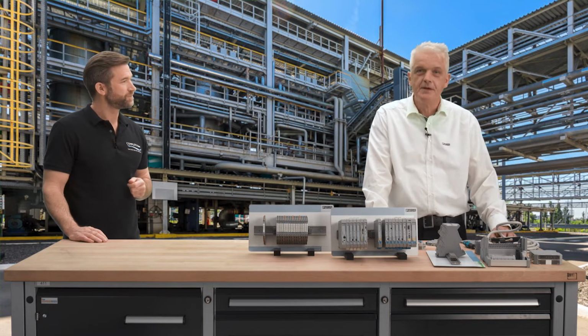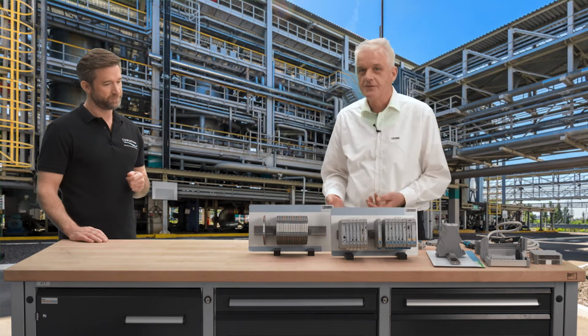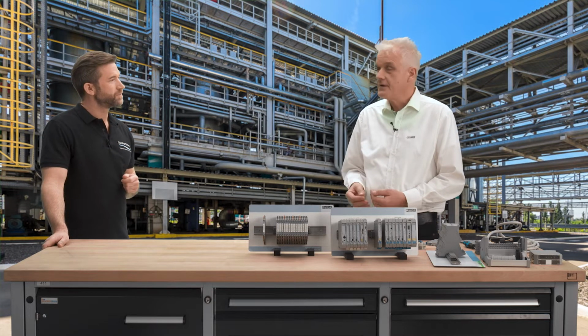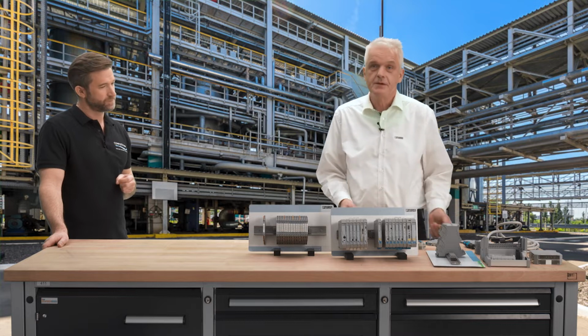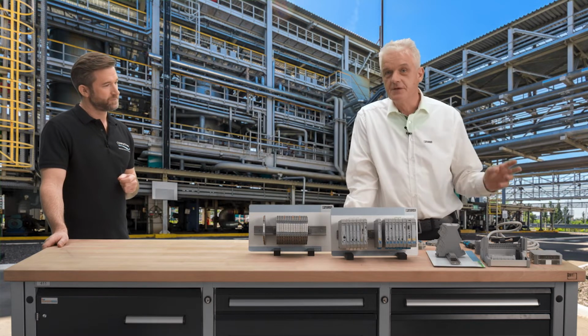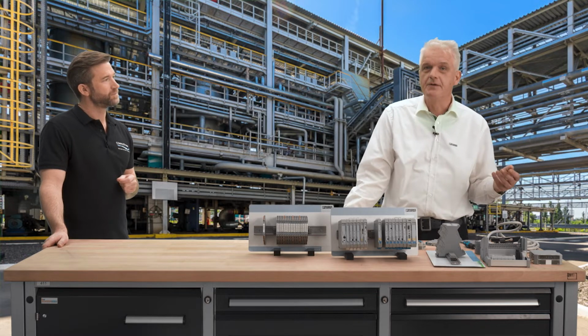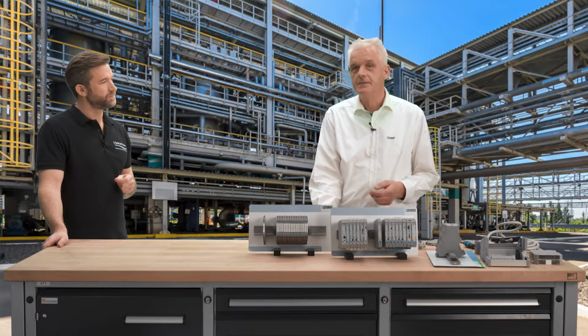Yes, of course. Signal conditioners fulfill, depending on the specific application, a variety of tasks. Signal conversion is the first one. The signal conditioners convert signals from the field device to a different type of signal which is required by the control system.